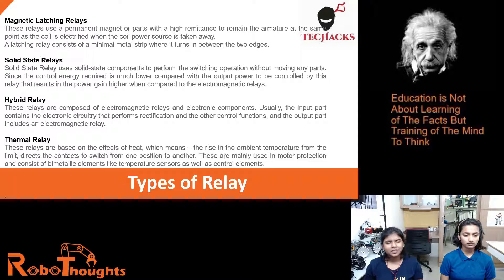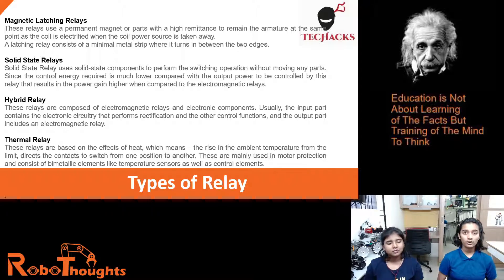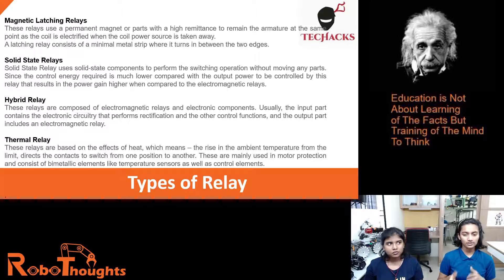Hybrid relays are composed of electromagnetic relays and electronic components. Usually the input part consists of electronic circuitry that performs rectification and other control functions, and the output part includes an electromagnetic relay. Thermal relays are based on the effect of heat — a rise in ambient temperature beyond the limit causes the contacts to switch. These are mainly used in motor protection and consist of bimetallic elements like temperature sensors and control elements.